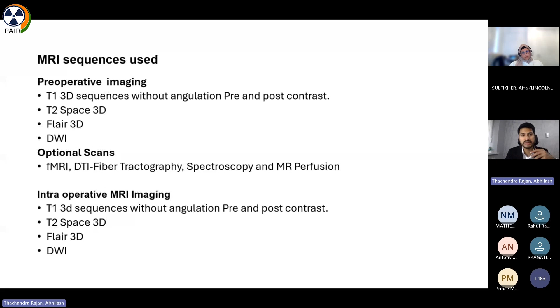These are the equipments used in the intraoperative MRI. We use a magnet. In our case, we use a 3 Tesla magnet because, for advanced neuroimaging, a 3 Tesla will always be good. That increases the potential risks as well. And the table is a special table. This is not the actual MRI table. This table doesn't have the spine coil or the spine element on it. So this table can be docked with the theater table, and the top of the table can be slid onto this table, and we can bring the patient to the MRI room and dock it to the MRI machine. We can proceed with the scans.